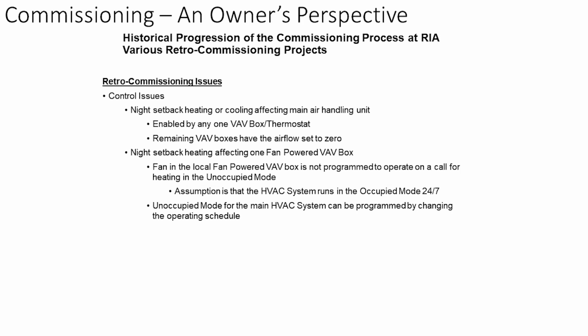Believe it or not, some of the buildings are programmed so that if one VAV box requires heating or cooling in the night setback mode, it starts the air handling unit. That's fine. But all the other VAV boxes are set to 0 airflow, so they all close. So I start a 30,000 CFM air handling unit for a VAV box that moves 300 CFM. Luckily, there are overpressure sensors.